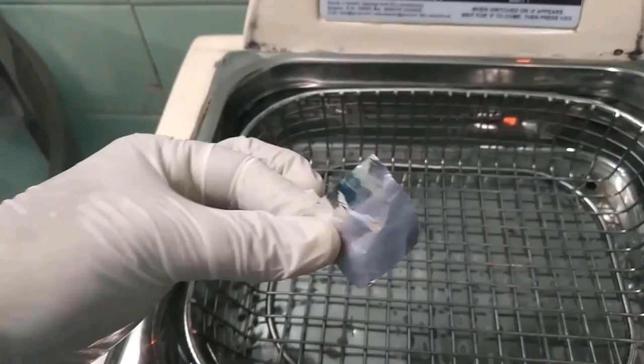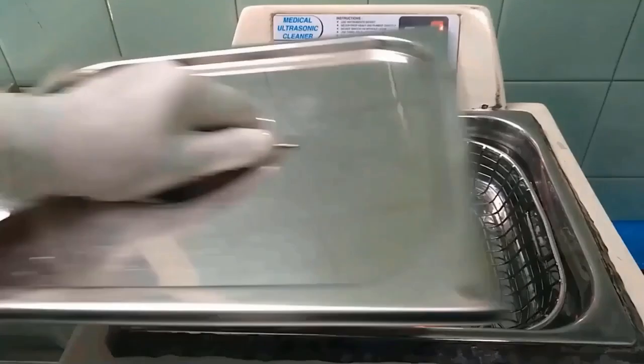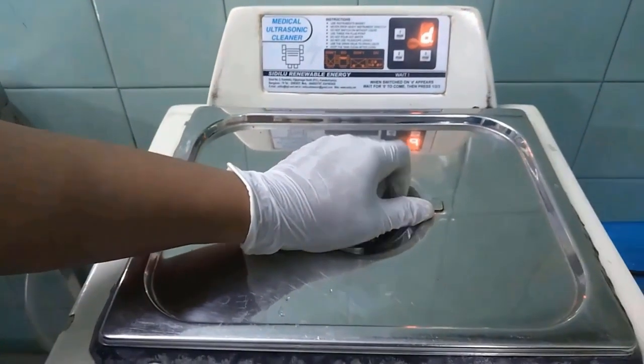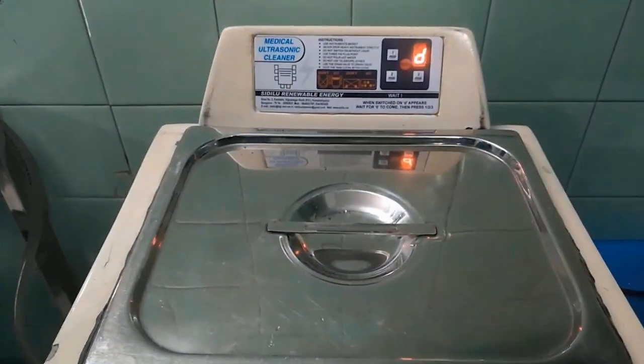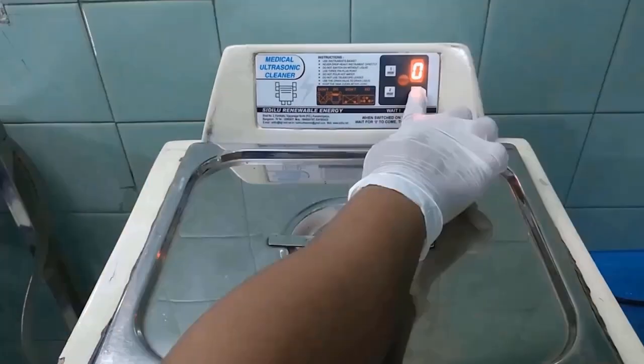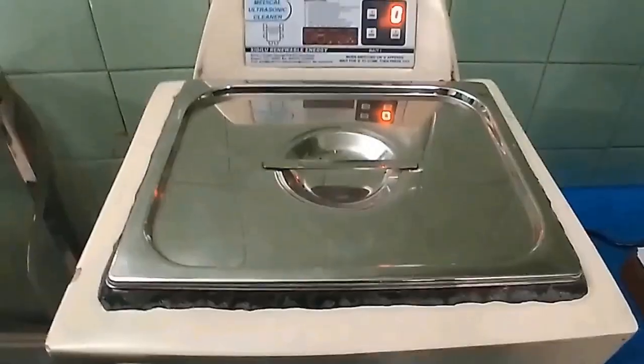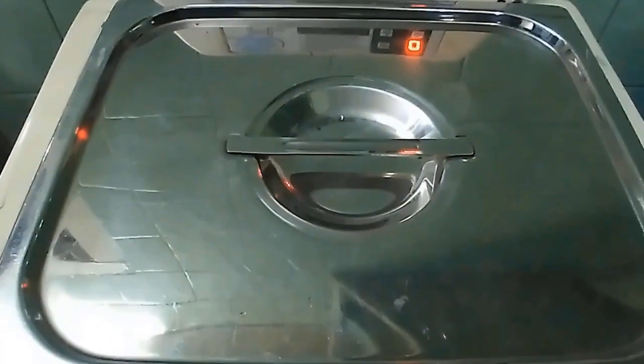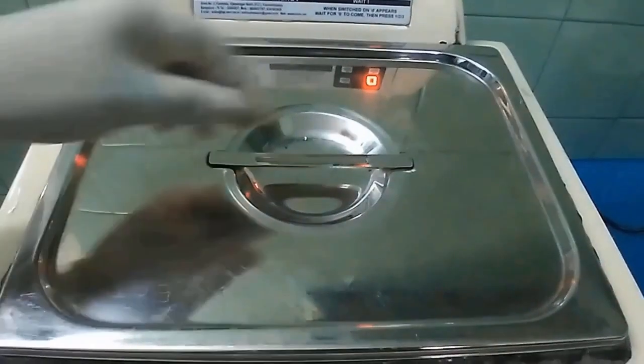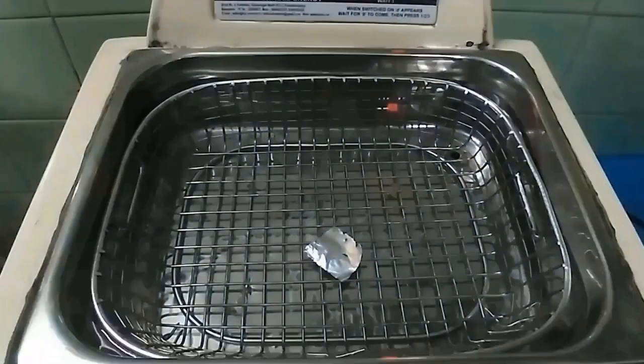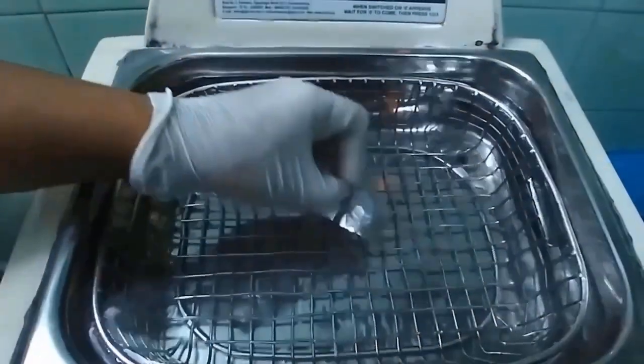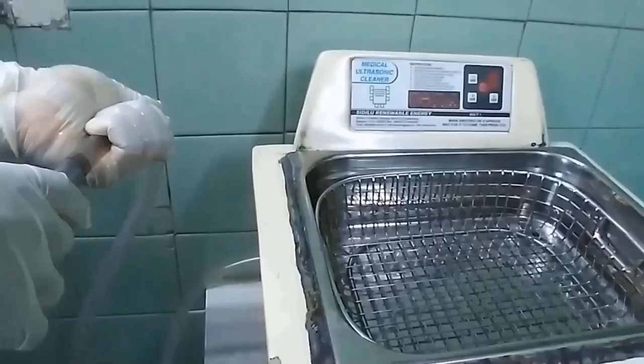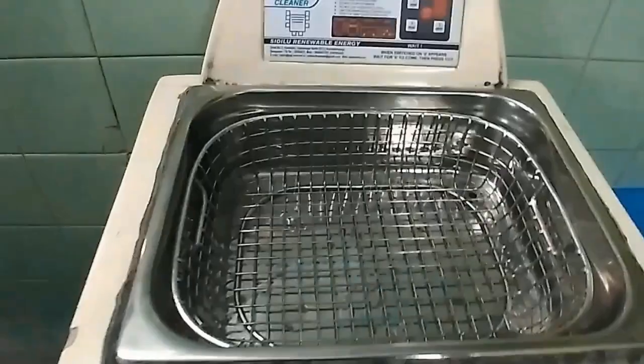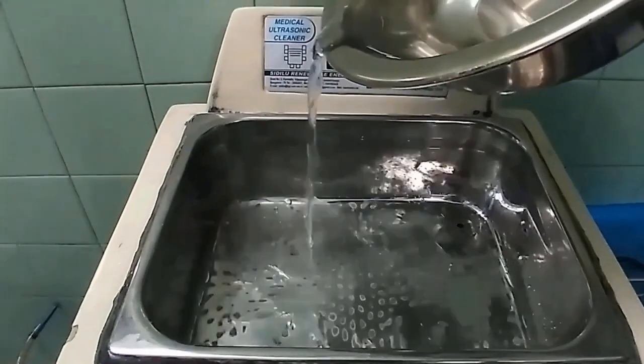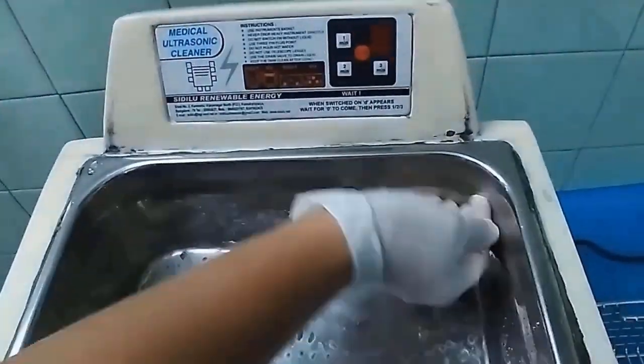To check the working status of the ultrasonic cleaner, put aluminium foil inside it and keep it on for 3 minutes. Due to the ultrasonic vibrations, the aluminium foil gets pores if the machine is functioning well. So after 3 minutes, check whether pores are present. If pores are present, the ultrasonic machine is working properly. After checking, drain all the water out and refill it with the correct amount of filtered RO water. Then keep the segregated instrument trays inside it.